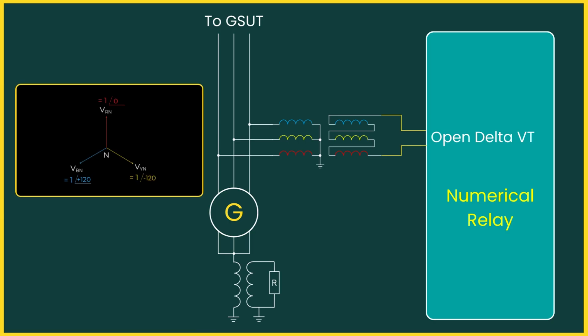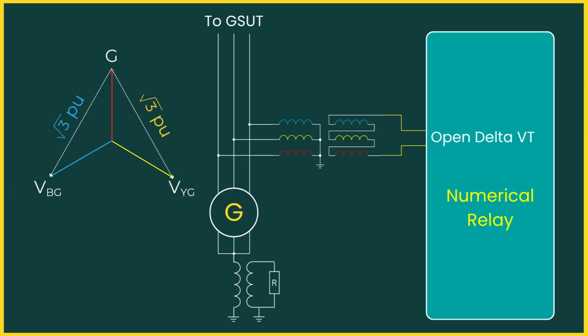Under balanced conditions, the voltages are symmetrical and the open delta output is 0. When an earth fault occurs, the system becomes unbalanced and a voltage appears across the open delta terminals, proportional to the neutral voltage displacement. This residual voltage is fed to the overvoltage relay, which detects the fault. To prevent the relay from being exposed to voltages beyond its safe input range, a specific VT ratio is chosen for this scheme. For a 22 kV generator, the correct ratio is 22 kV/√3 to 110/3.